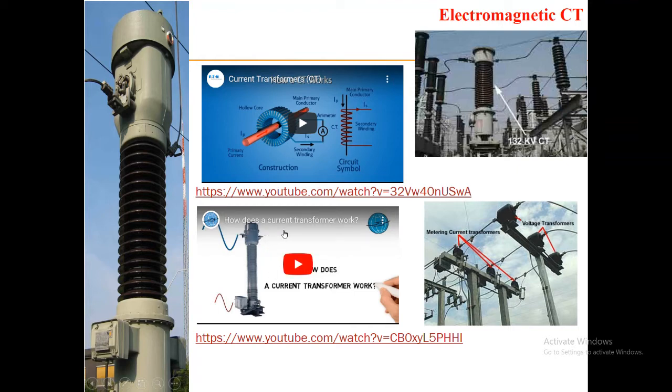Current transformers are used to transform standardized primary currents into standardized secondary currents. The AC currents converted this way are much smaller than the primary flowing currents and can be directly processed by the connected protection, control, and measuring systems. In this video, we look at the basic operating principle of an inductive current transformer. The basic principle is simple electromagnetic induction.